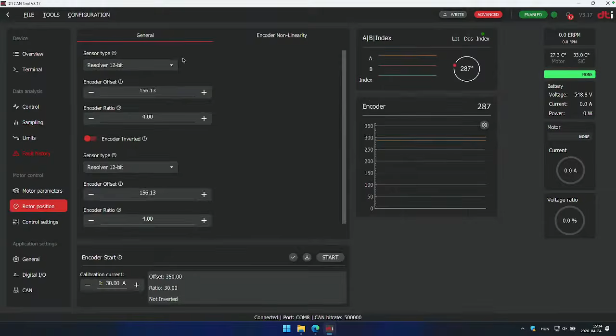Let's get back to the encoder nonlinearity. I'll show you how much you can improve with this. I'll go to a stabilized RPM, let's say 7000 RPM, click the Now button and download the sample. It's important that the RPM is stabilized, because if it's changing, it can lead to nonlinearity curve deformities which are avoidable. Right now we can see these waveforms, and we can decrease them based on rotor position with the encoder nonlinearity calibration.